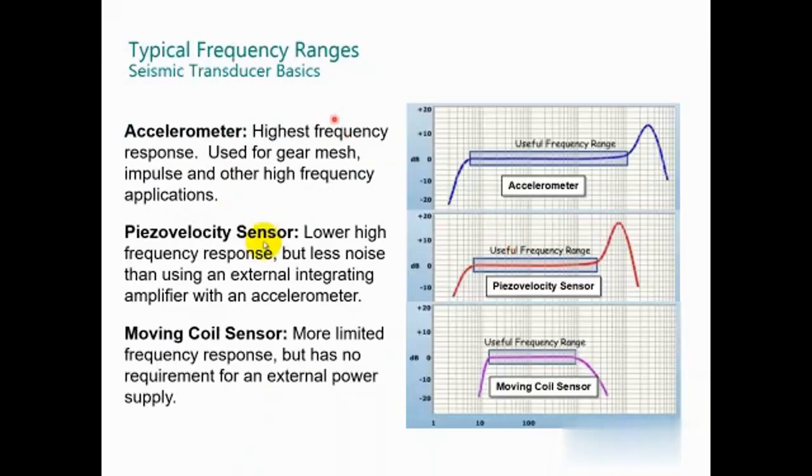From the aspect of frequency, the accelerometer has the highest frequency of up to 20 kHz and the minimum is around 10 Hz. The piezoelectric velocity has a lower high-frequency range, around 5000 Hz with minimum of 10 Hz. For the moving coil, it's more limited - the frequency is until 1000 Hz, and the starting depends on the design from 10 Hz or even lower frequency.